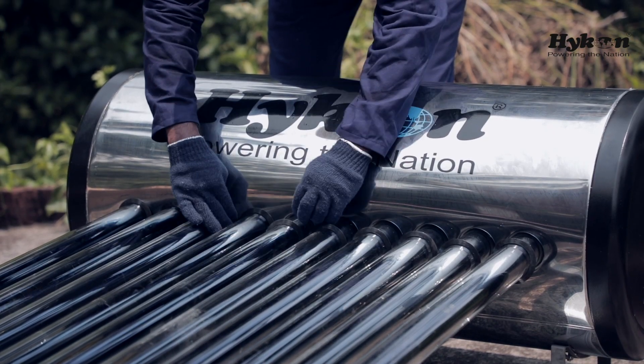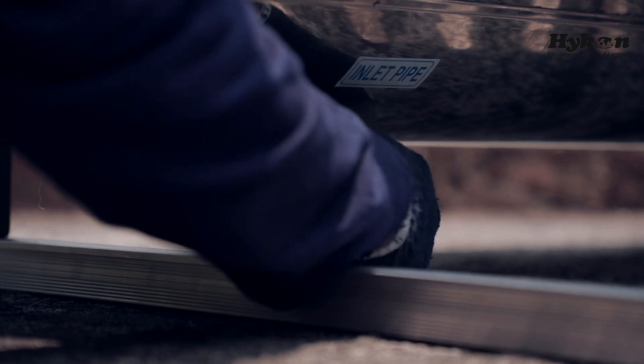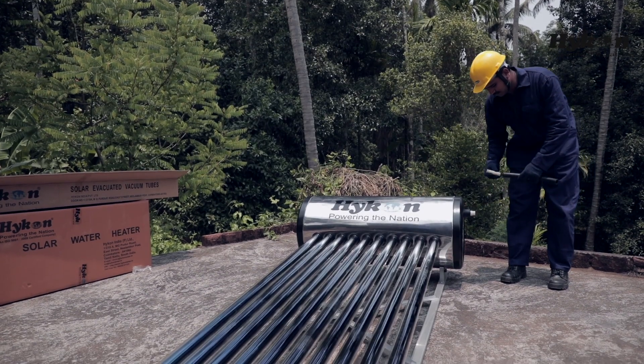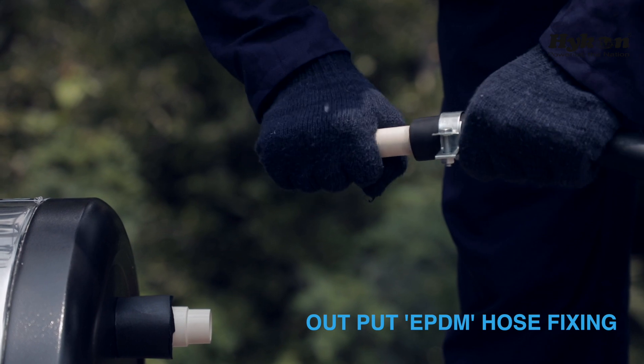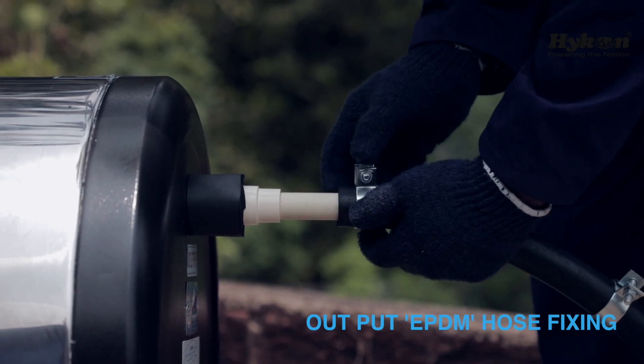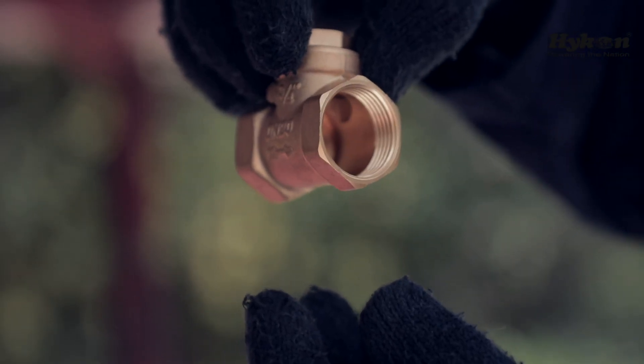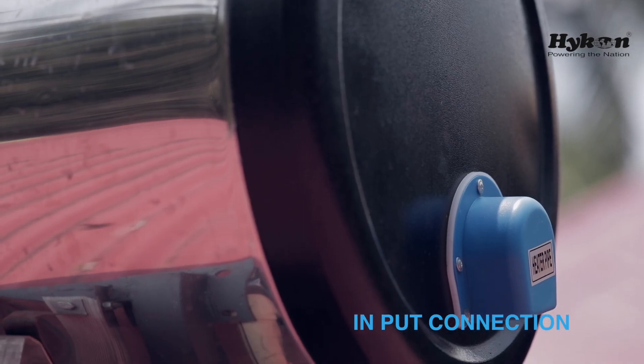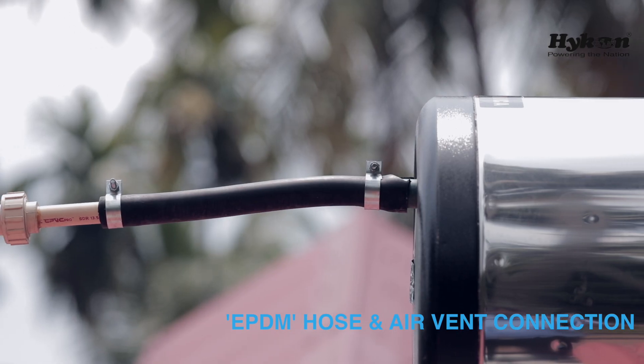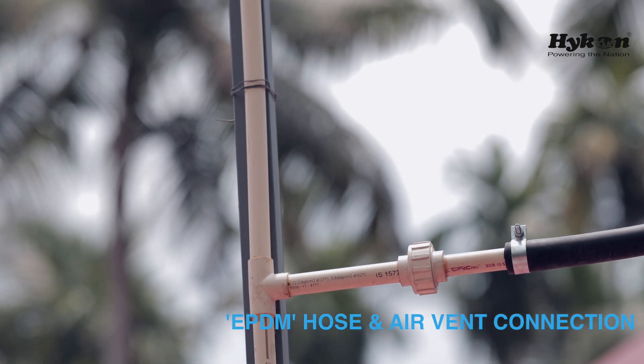Now we have to connect the outlet of the tank to the distribution line by fixing the EPDM rubber tube, which is connected to the air vent pipe. Please don't forget to fix a shutter type horizontal non-return valve at the inlet. EPDM rubber hose and air vent connections are must — they are a protection for the tank.